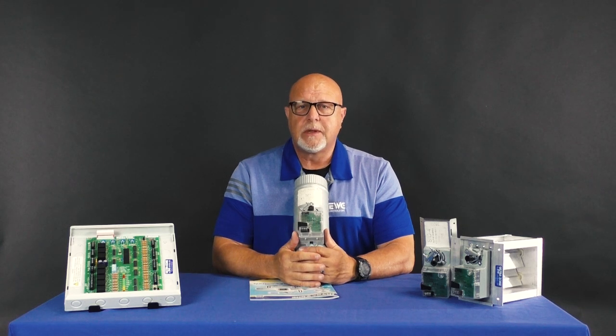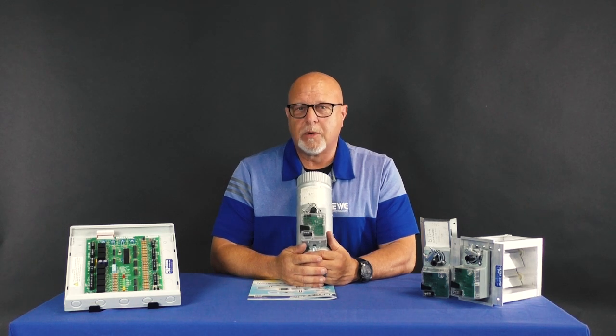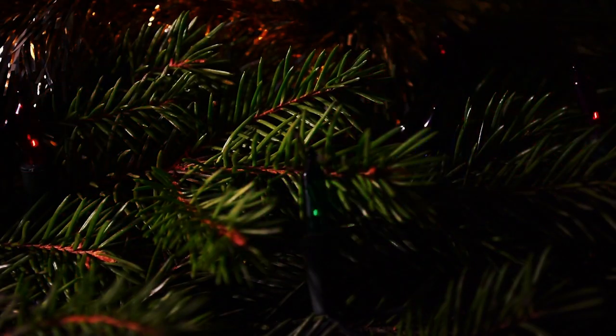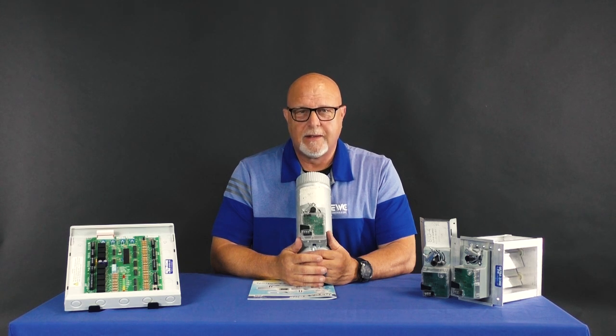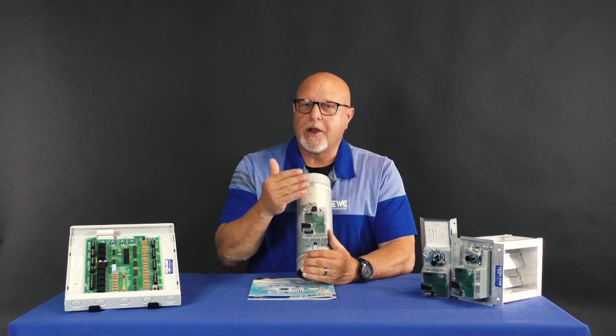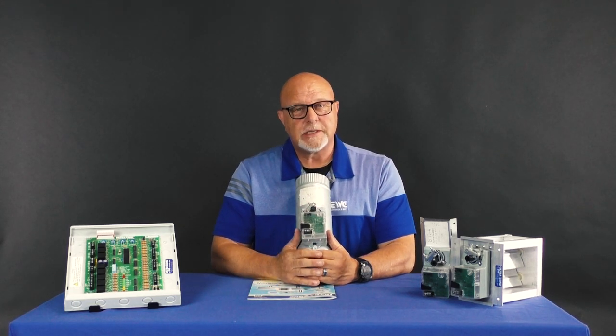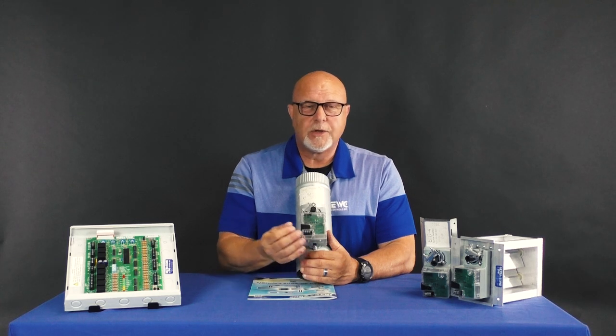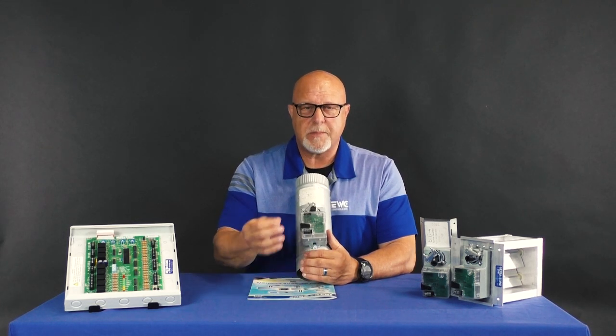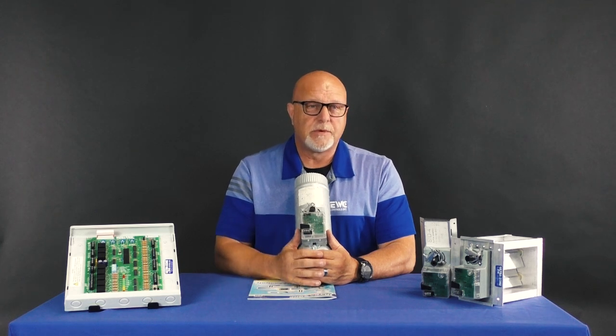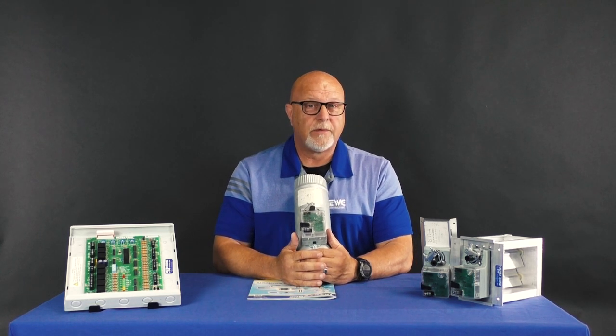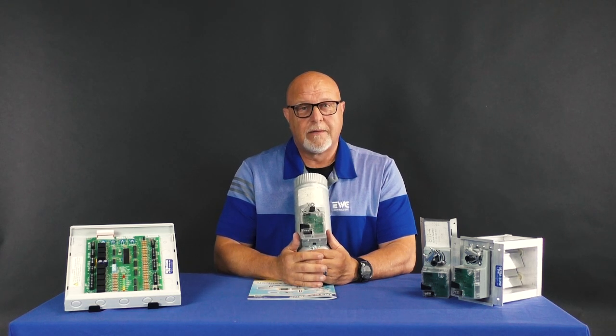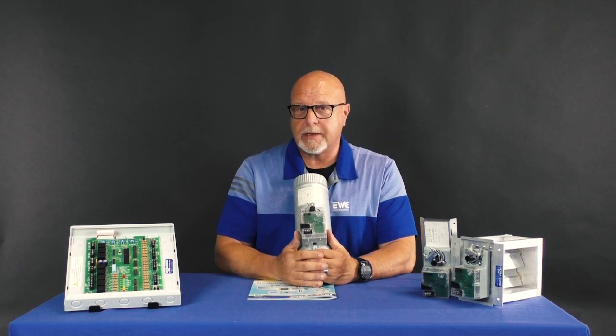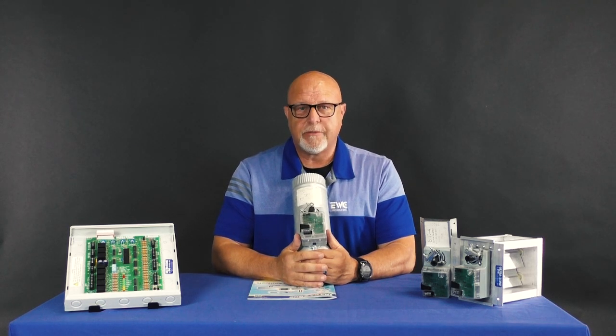When you wire these dampers in a daisy chain or series type situation, they operate very similar to the old style Christmas tree lights. If you had one bulb that was broke, the whole strand of lights would be dark. You had to find that one bulb and replace it, and then all of your lights would come on. This operates very similar. If you have a loose wire or a loose connection or a cross wire on the EWC wiring from damper to damper, then if you have 6 dampers in that series and only 3 lights are illuminated when they are supposed to be, you know exactly where that short or that miswire or loose wire is. Obviously it's somewhere between dampers 3 and 4.